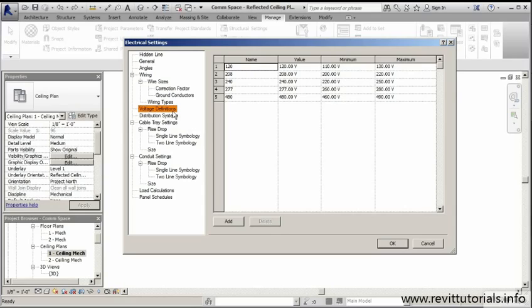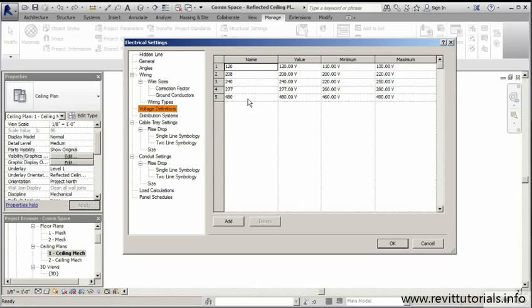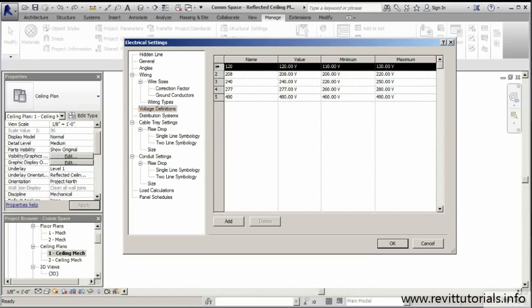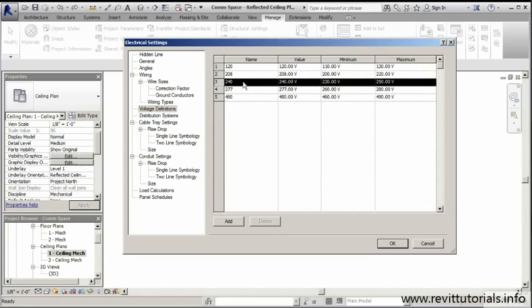that's when we'll need a special breaker that can handle higher equipment capacity. We're also going to have to have special GFCI switches, according to code, in areas with high moisture. I'm definitely going to keep this in mind when we're setting up our distribution center. You can see we've got a nice wide range of voltages to work from here. You can see our 120 here, which we'll definitely be accessing, and our 240. There's also a min and max associated with that. I think that calculation is maybe 10% below our voltage and then 10% above.